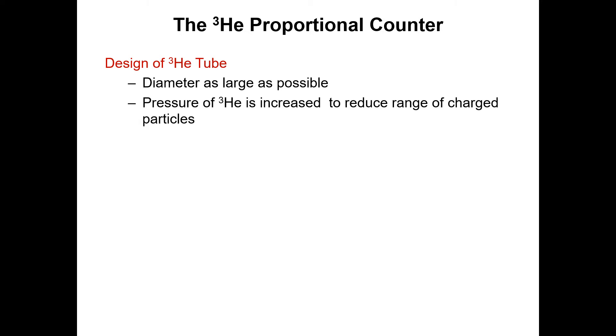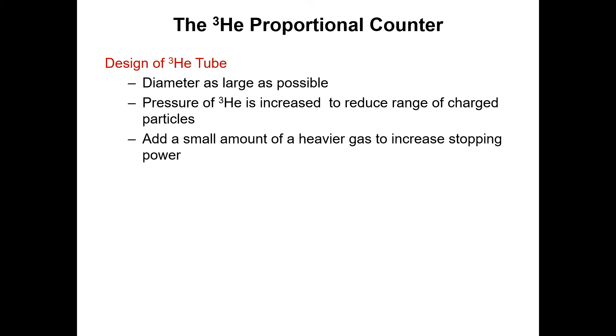Now, the helium-3 proportional counter — what is its design? Just like previous gas-filled detectors, this kind of detector has a diameter as large as possible; we use a larger diameter compared to other gas-filled detectors. The pressure of helium-3 is increased to reduce the range of the charged particle. To increase stopping power, we add a small amount of heavier gases.